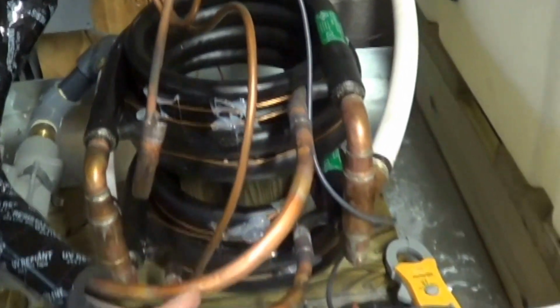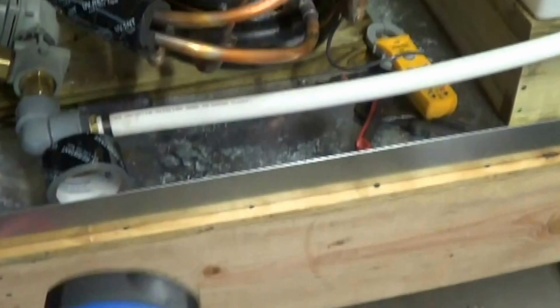Alright, so we got the 2 coils in parallel, but you can see here on the thermal, the subcooling's too high. It's only using the first few loops for heat exchange, and all the rest are liquid, and the head pressure's still jumping up too high as it switches cycles and it's tripping on the high head. So I got to take charge out.